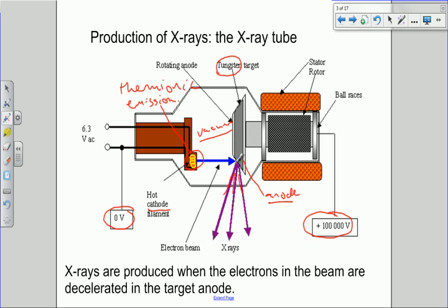That would make the tungsten very hot in this position, because you'd have a stream of uncountable numbers of electrons hitting this part of the tungsten target. The way it's kept cool is to rotate this at very high speed. It's connected to a very large high-torque electric motor, which rotates this thing rapidly. As it rotates, it prevents the electrons hitting one part of the tungsten, and enables them to effectively be spread out over the entire area of the tungsten target. That is one of the ways in which it is kept cool. It's also sometimes oil cooled as well.